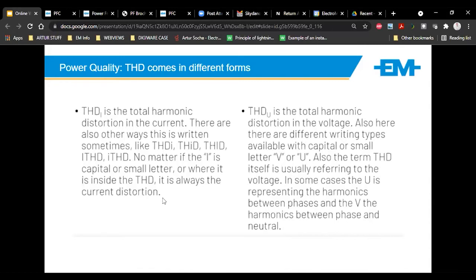Sometimes you can get distorted voltage harmonic from your utility or your grid. The only real way to see that is very high-end power analyzers. The simplest way to see it is if you've got a basic power analyzer and your loads are off, but you're getting a voltage harmonic, you know it's coming from your neighbor. So if you had a neighbor that's got some spot welding and a whole lot of VSDs, irrigation, or you could be next to some massive pumping site that's got a lot of variable speed drives, you might start seeing voltage harmonics coming through onto your grid. But inherently it's all caused by a load.